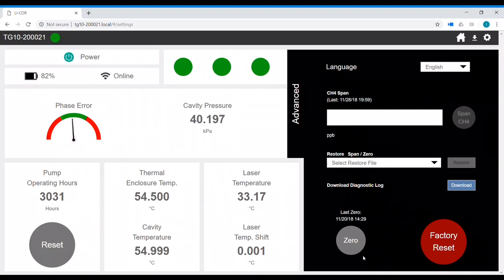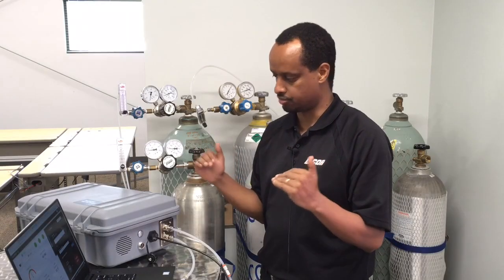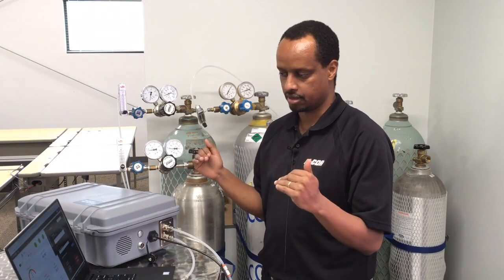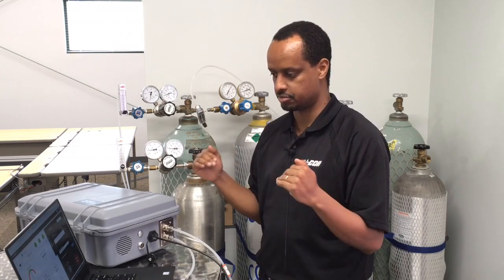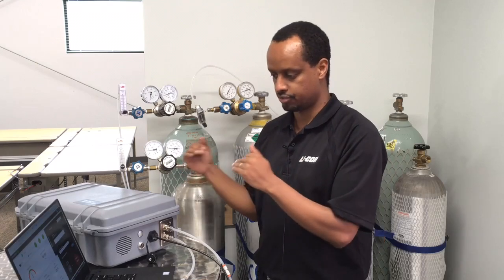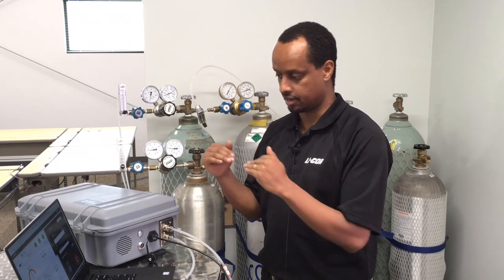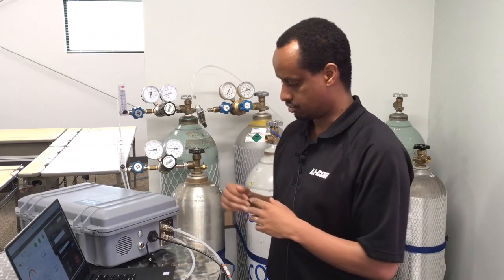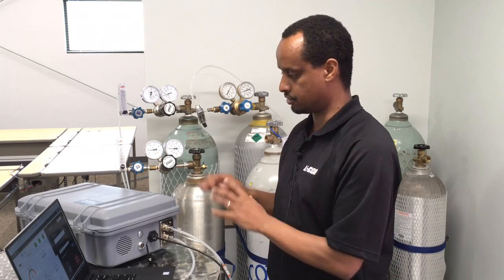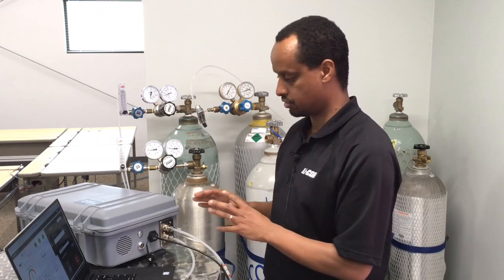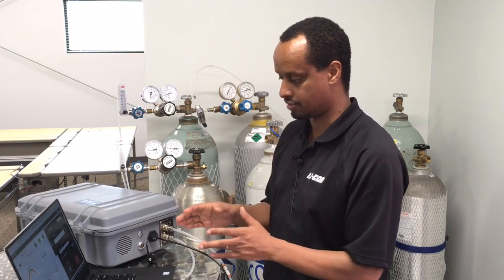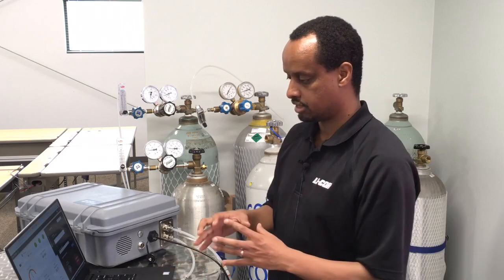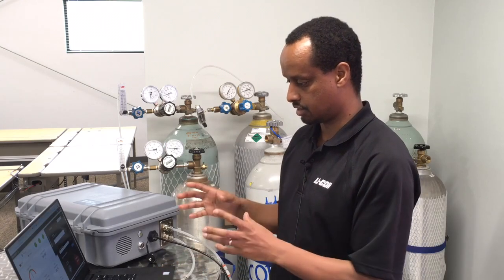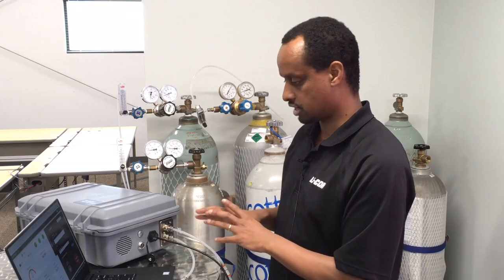And when we click this button here, 0, what happens is the instrument is going to record the absorption spectrum with 0 gas flowing and take several minutes of reading and use an average spectrum as the baseline spectrum. So all future measurements will have that baseline spectrum subtracted from them. So you don't want to change any of the flow settings or the plumbing or the instrument settings when it is doing that averaging. It's going to take about 4 to 5 minutes. Once you click 0, the instrument will stop outputting data to the screen, and it will just tell you to wait, and you don't want to change anything in that period.